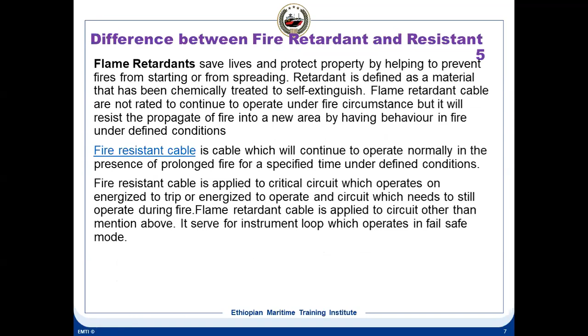And fireproof glands to be used in case of cable passing through the bulkheads. So the cable glands have to be fireproof. So these are a few methods, maybe some more, so that the spread of the fire can be reduced by installing the cables. Okay. So hope you understood fire retarding, flame retarding, and fire resistance. What is flame retardant cable? What is fire resistant cable? Both are two different things.